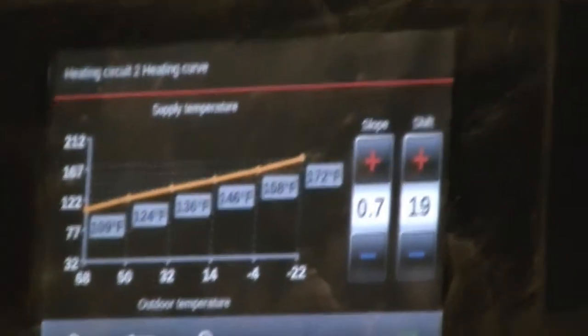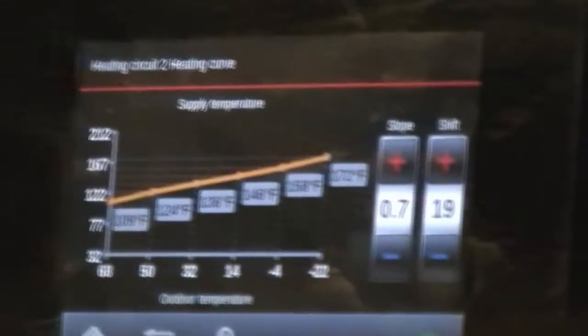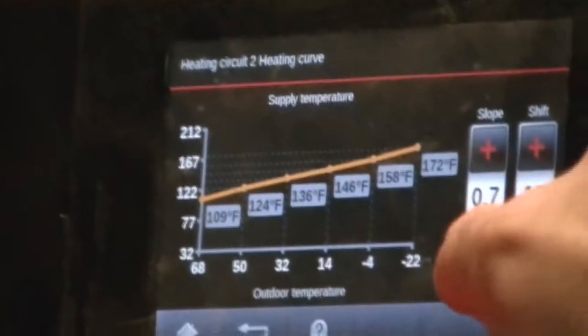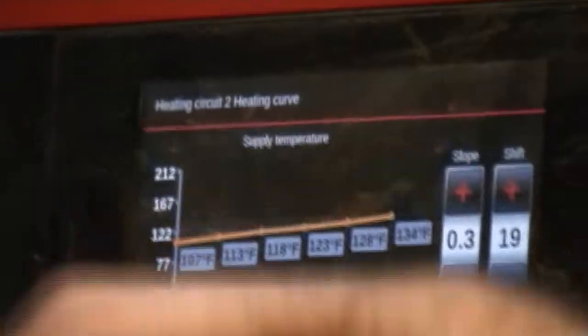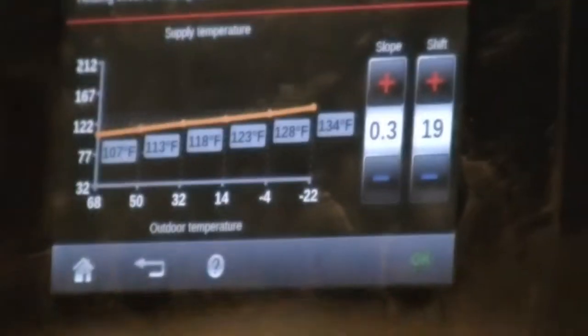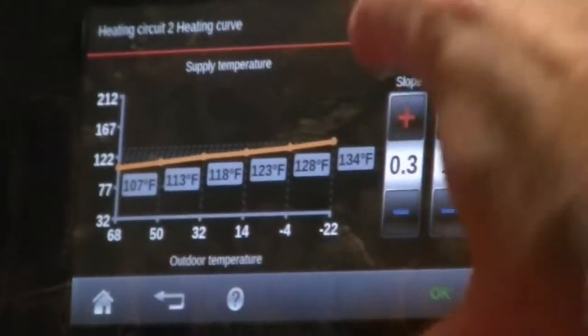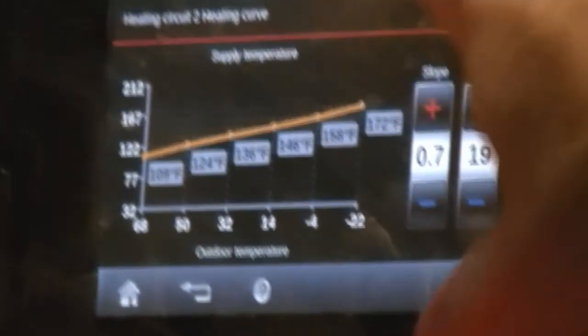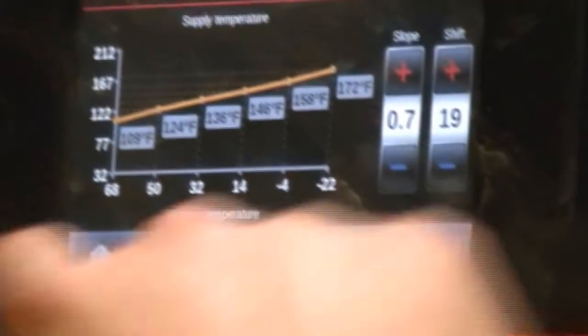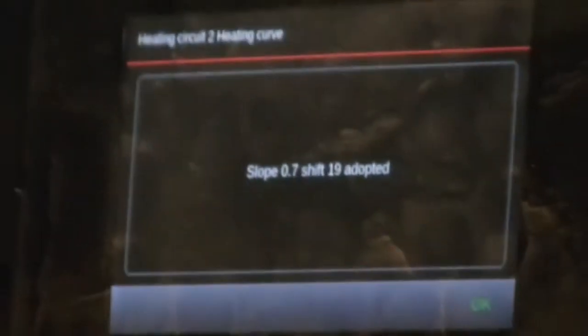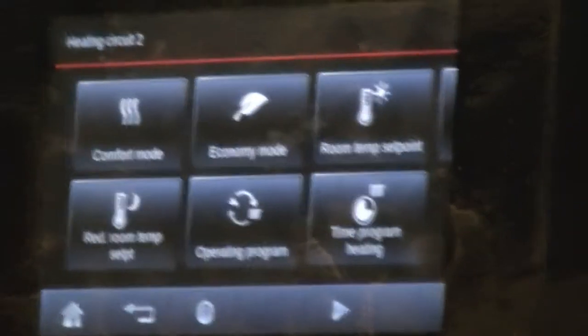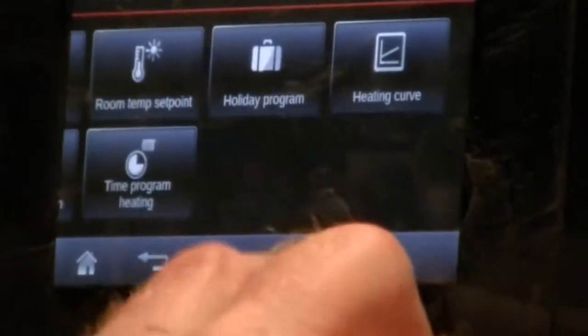Now, you don't really have to care what those numbers mean, because as soon as you start to touch them, you'll see that curve shift up or down. So you get that to the temperature you think you want based on your outdoor temperature. You get it at a 0.7. And once you get it to where you want it, you hit the OK button. Okay? Now you can go back to the main screen if you want, or eventually it'll go back to the main screen on its own.